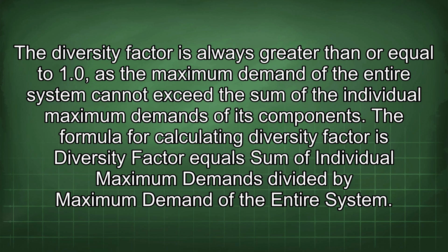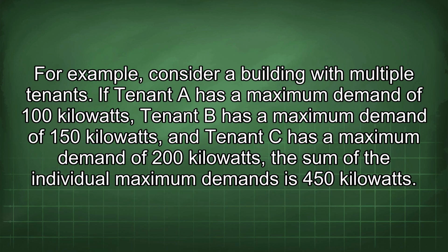The formula for calculating diversity factor is diversity factor equals sum of individual maximum demands divided by maximum demand of the entire system. For example, consider a building with multiple tenants.